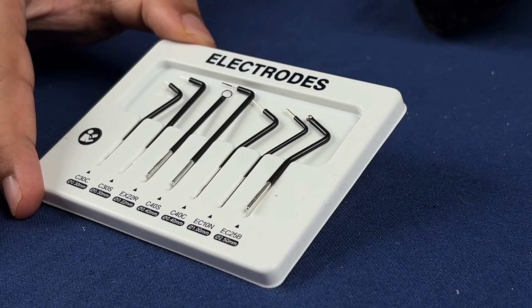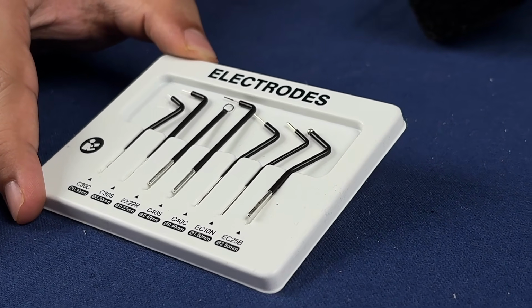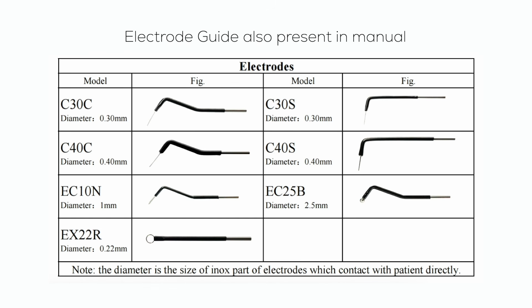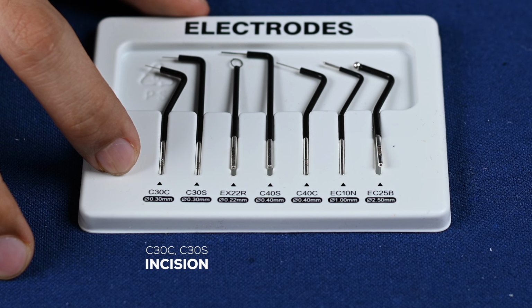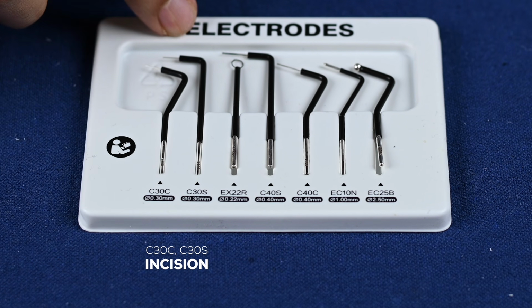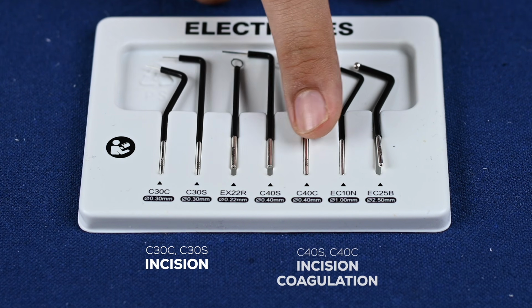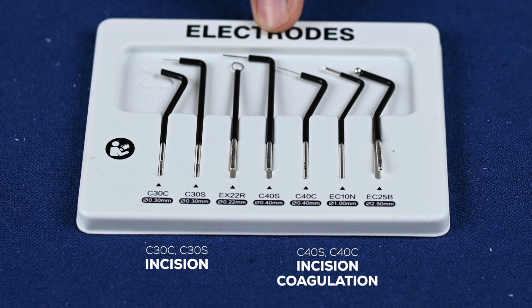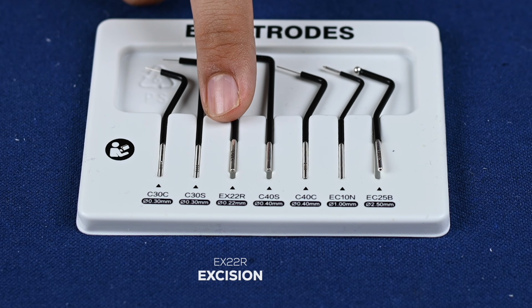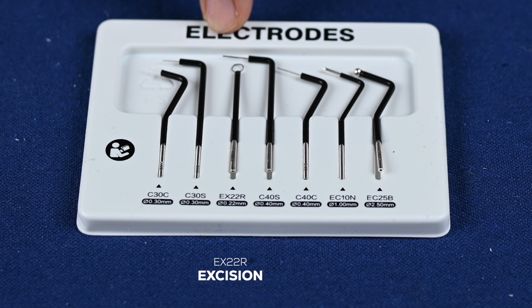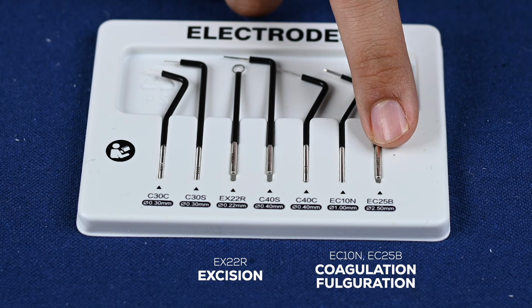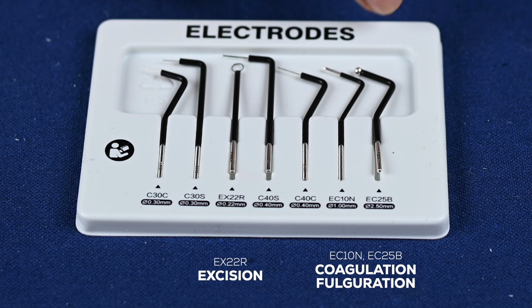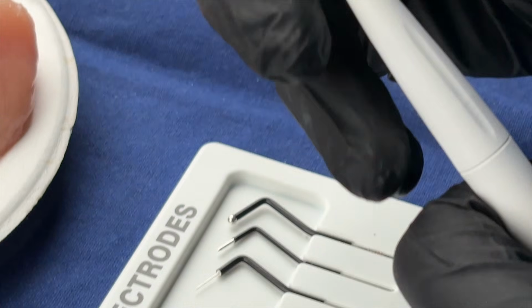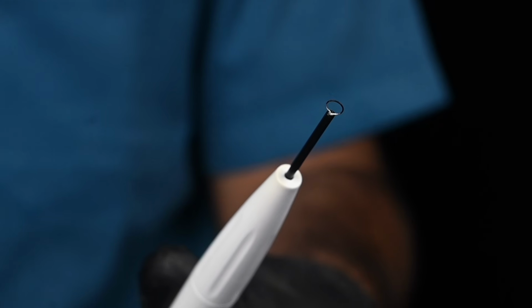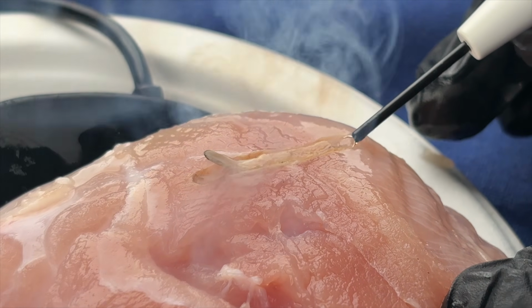So with this electrosurgery unit, we get these 7 electrodes. The model number and diameter of the respective electrodes is mentioned here. Electrodes C30C and C30S are used for incision only, whereas C40S and C40C are used for incision coagulation. On the other hand, EX22R is used for excision or depigmentation, whereas the remaining 2 electrodes are used for coagulation and fulguration. Now we will see the excisional action, which can be used in a depigmentation-like procedure using the loop electrode.